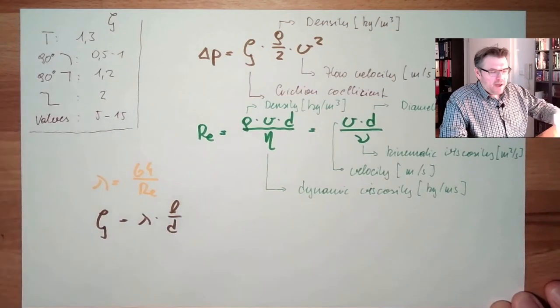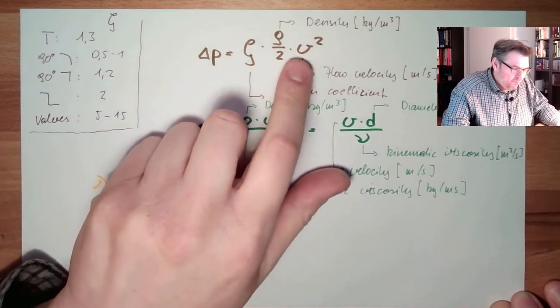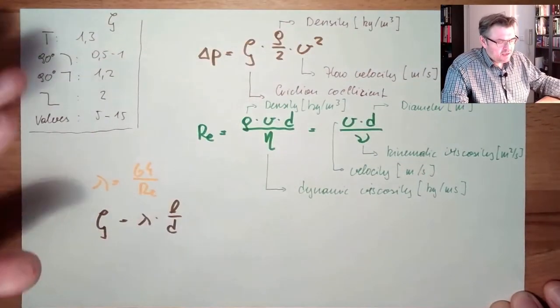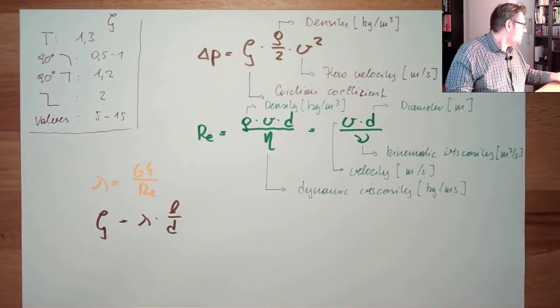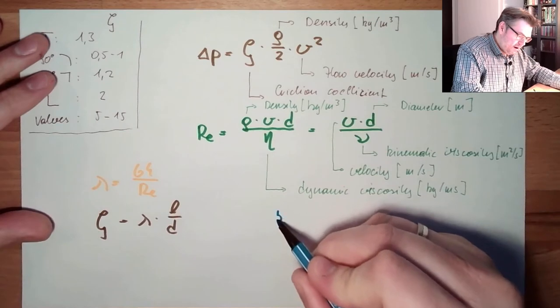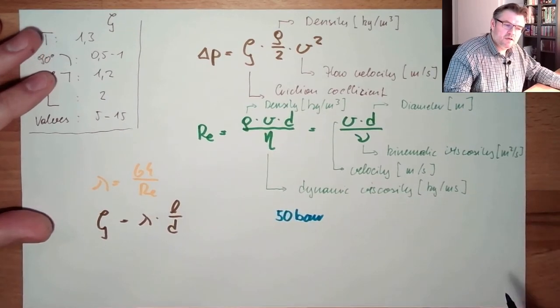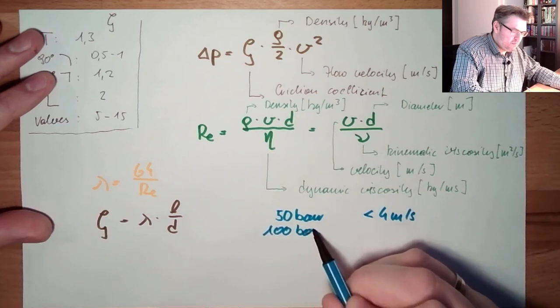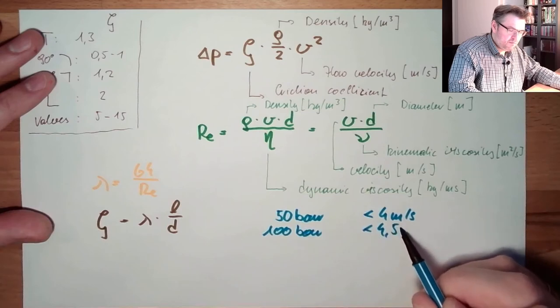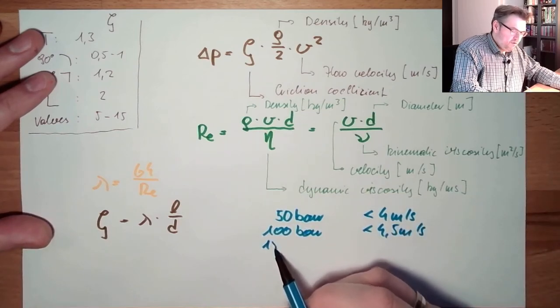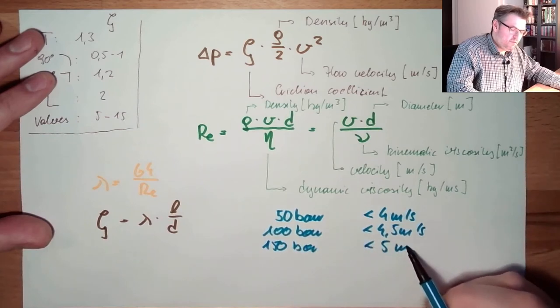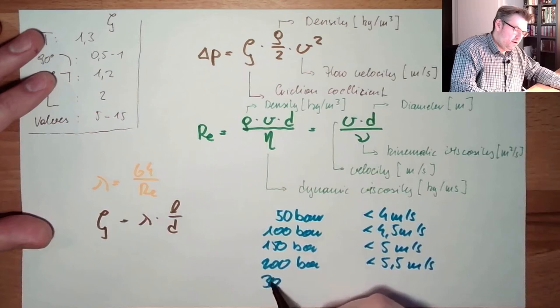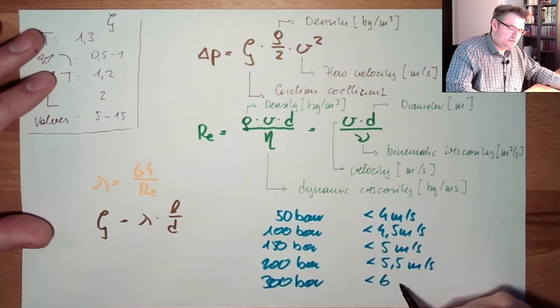Depending on the pressure level, if we are below a certain flow speed, we are in laminar streaming and can calculate the pressure losses. The rule-of-thumb limits are: at a 50-bar system, flow velocity should be lower than 4 m/s; at 100 bar, lower than 4.5 m/s; at 150 bar, lower than 5 m/s; at 200 bar, lower than 5.5 m/s; and at 300 bar, lower than 6 m/s.